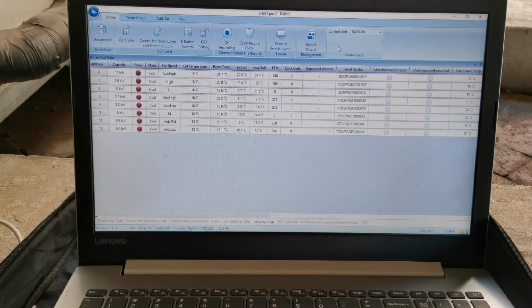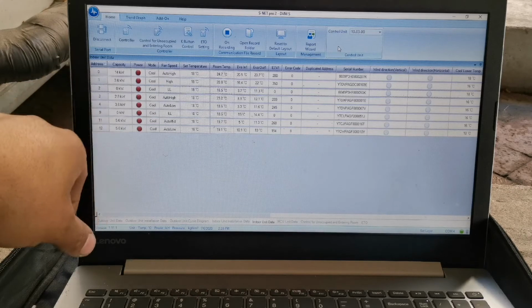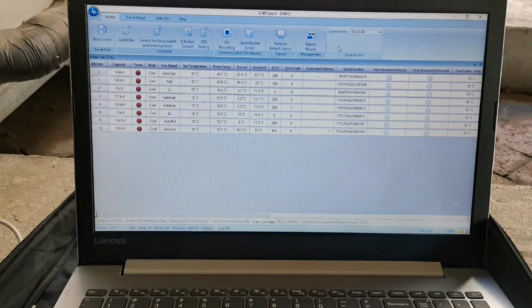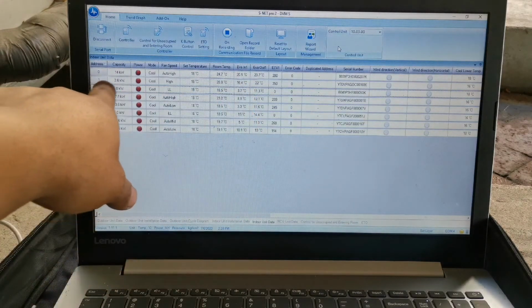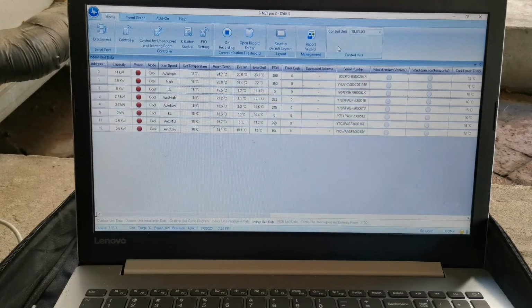Okay, so it's been about 10 minutes. We've switched system address 0 and 1 on cooling. As you can see, there is cooling capacity, and the expansion valves have started opening as well. The biggest change I can already see is on address number 1, which would be the ductless midwall. We've got 16.4 incoming, 22 outgoing, and the room temperature is dropping as well. We are starting to see a small drop on address number 0, which is the cassette, the 4-way blower, but very minimal. So we're going to give it another 5 minutes to run and then see if there's any changes.